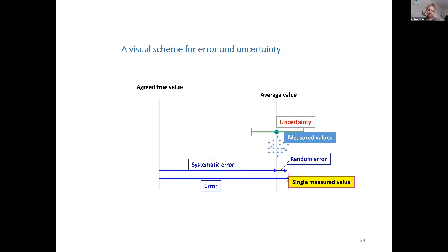Then you have your statistical distributed uncertainty, and you can apply the correction. Because now I add all the random information. Maybe I also have some type B uncertainty due to the measurement instrument, the procedure and so on. But when I go after the correction, I still bring myself the uncertainty. It is not just eliminated. It is still there, but now after I corrected for the error through the calibration, my value is, now I can say that, finally, it's accurate.